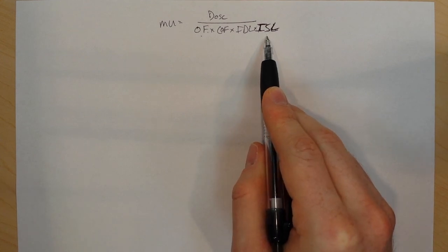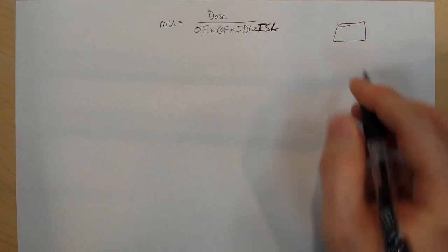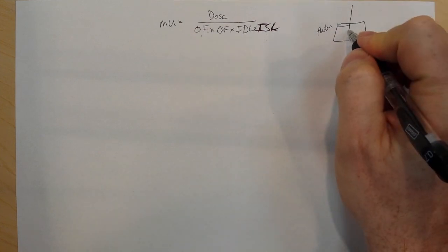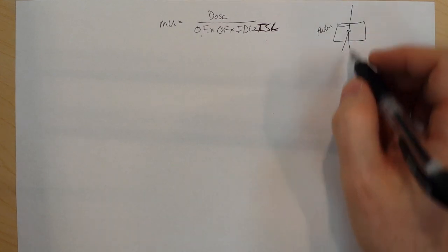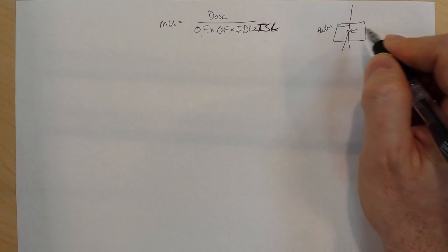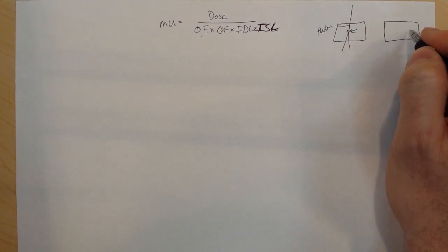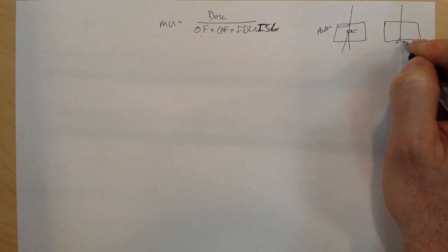But with electrons, there is no point source. In the treatment head of the machine, for photons, the electron beam comes down out of the bending magnet, hits the target, and then you get the shower of Bremsstrahlung X-rays below. This becomes your point source for the X-rays. For electron treatments, that target is moved out of the way. Electron beams come out of the bending magnet. There's no target. They come straight until they hit the scattering foil, and then you get a shower of electrons.